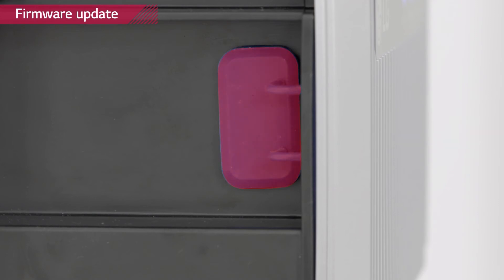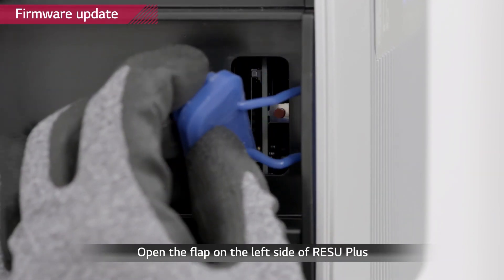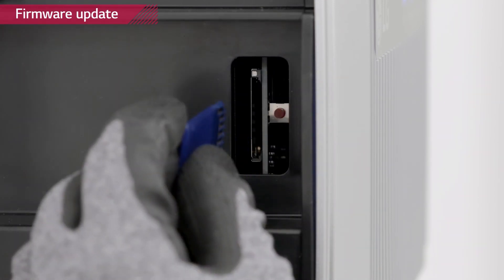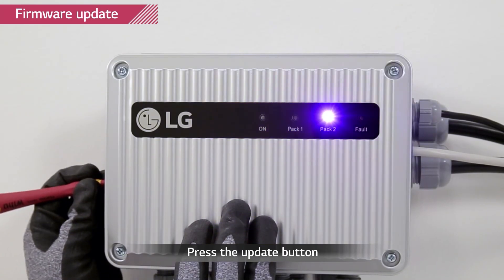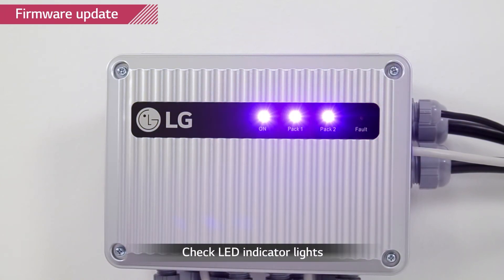For firmware update of RESU Plus, LG Chem recommends using one of the SD cards stated in the installation manual. Open the blue rubber cover on the left side of the RESU Plus. Insert the SD card and press the red button for three seconds. The lights will begin to flash from left to right. When the update is finished properly, the three lights will be lit at the end.